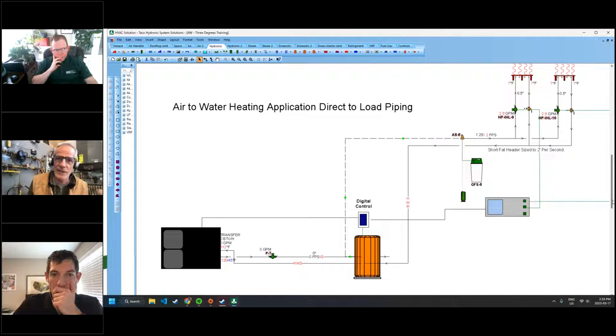It's not stirring the tank. It's not going through the tank up and down this way. It's going straight across. So you're going to get your lowest possible temperature to keep your COP up, or to keep your modulating boiler efficiency, your condensing, up. And then you're going direct to load on the top. So you're taking that most precious water that you just paid to heat or cool, whatever condition it's in, directly to load without going across a tank where you're going to lose some of it, because it's going to mix with something as it crosses through there.